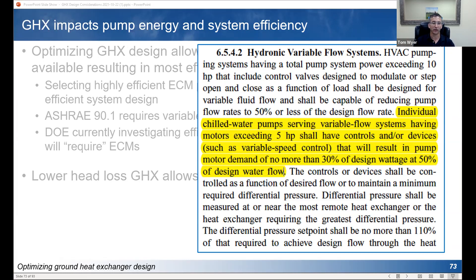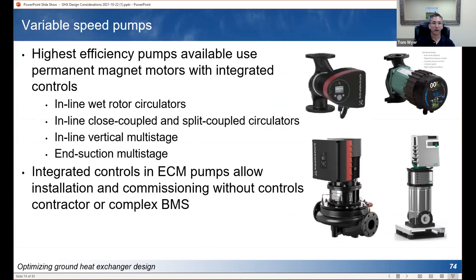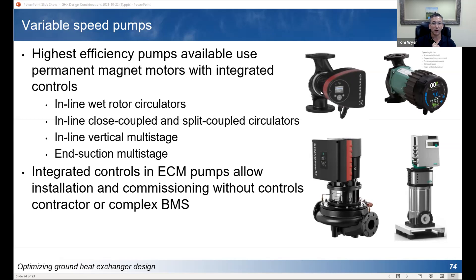The DOE is currently conducting an investigation looking at efficiency limits on pumps that may not specifically require ECM pumps, but the standards will be so high that you'll effectively be required to use some kind of ECM pump technology with variable speed. Having a low head loss design allows you to pick the highest efficiency pumps available — those that use permanent magnet motors with integrated controls. Over the last few years, manufacturers including Grundfos, Taco, Wilo, Bell & Gossett, and Armstrong have all brought permanent magnet variable speed ECM pump technology to market, and you can get pretty much every design of pump with ECM technology today.